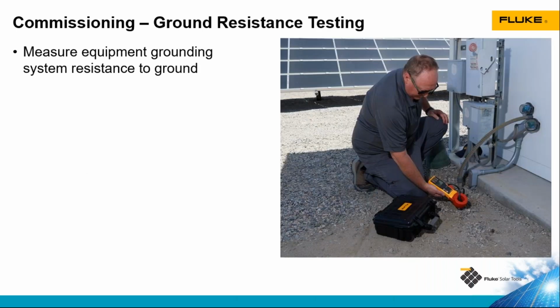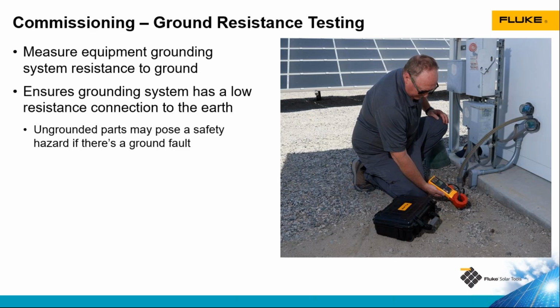A somewhat related test is ground resistance testing. This is making sure that our ground rod or grounding electrode has a good bond to the actual soil. Same reason we do the last test, making sure that current has an easy path to the ground. We want low resistance there so that we don't have any safety hazards from energized metal parts in the system, and also to ensure those overcurrent protection devices are working properly.